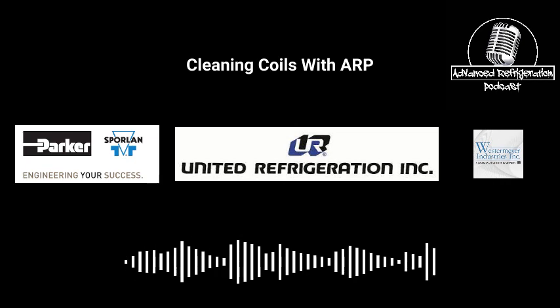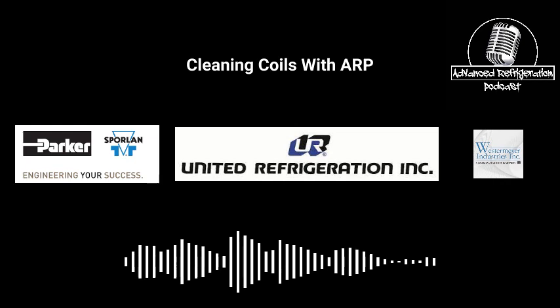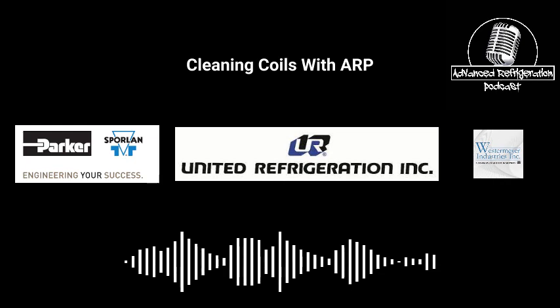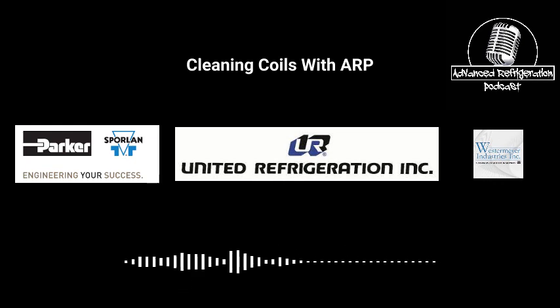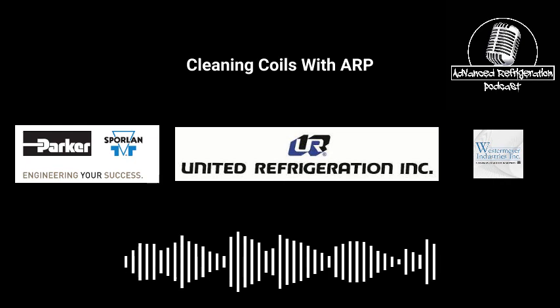Dirty fan blades can cut your airflow down 10%. Not to mention, it makes the blades go slower, or the motors go slower, because they load up more because they have more weight on there. So clean the blades and clean the fan guards and clean around the fan guards, because let's be honest, the customer 90% of the time doesn't look at the back of the coils. I mean, they need to be clean, but what do they look at? They look at the fan guards and they look at the face of the coil and the blades. If they see that's dirty, even though you may have cleaned that coil very well, it looks like you didn't do your job. So just keep that in mind.